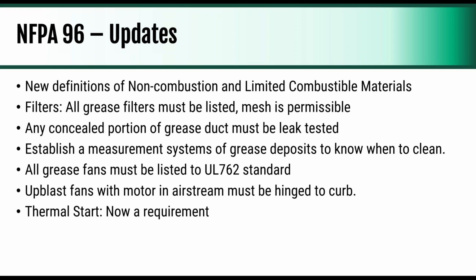Another thing was establishing a measurement system of grease deposits to know when to clean them. Previously, NFPA 96 had provided some guidance, which I would say was pretty good before, but as always, open to different interpretation. So they basically developed a system now where they measure the grease deposits to know exactly when that duct needs to be cleaned, to provide guidance. All grease fans must be listed to the UL 762 standard. Again, most municipalities have been requiring that anyways.